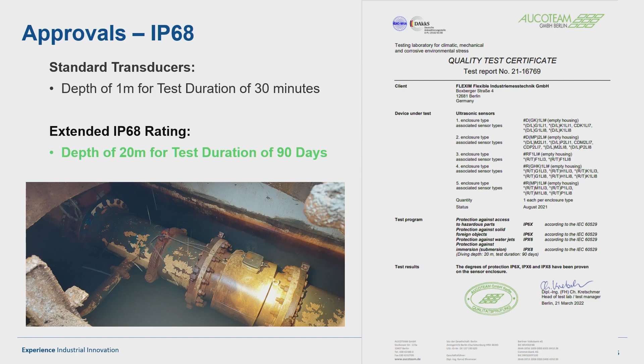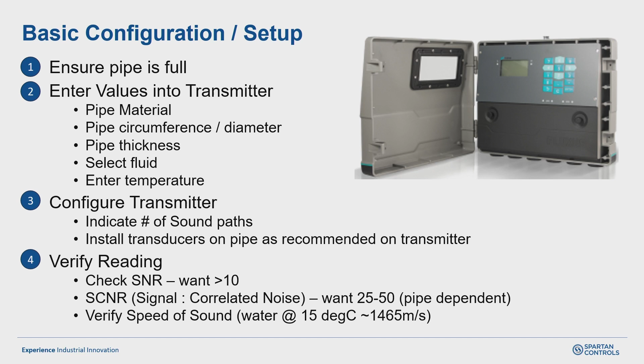So not going to spend too much time on this, but basically this is the procedure for setting one up. We essentially want to input the pipe material, pipe thickness, that kind of stuff into the system. Then we configure the transmitter for the number of sound paths we're putting in, and check a couple of diagnostics to make sure it's looking okay. One of those diagnostics is signal to noise ratio, we want that number to be over 10. Then there's signal to correlated noise ratio, we want that somewhere between 25 and 50. And we want to make sure the speed of sound is somewhere in the ballpark of 1,400 meters per second.